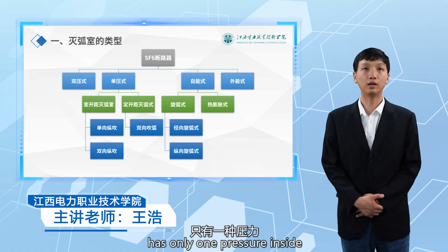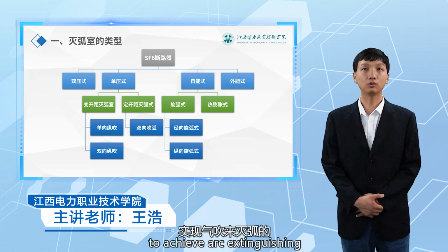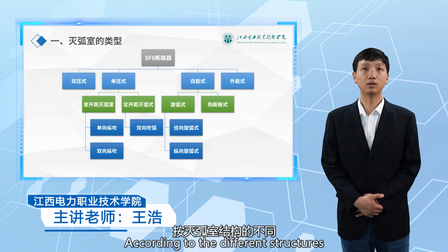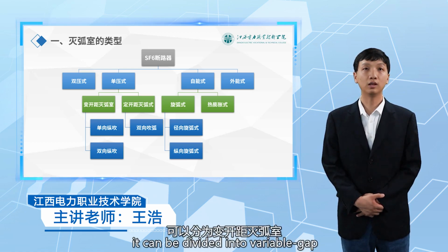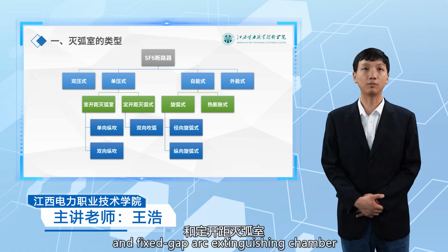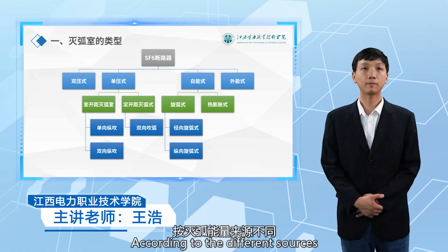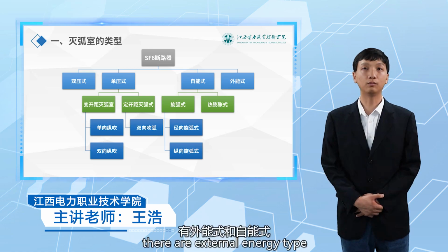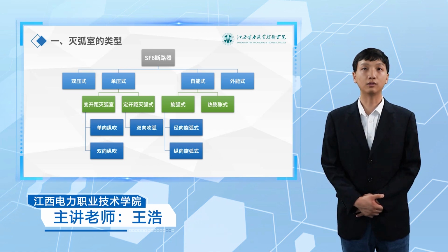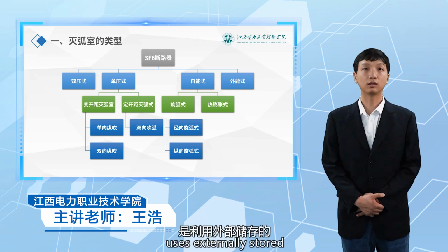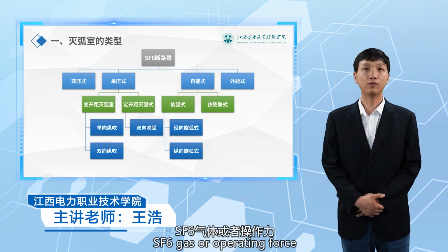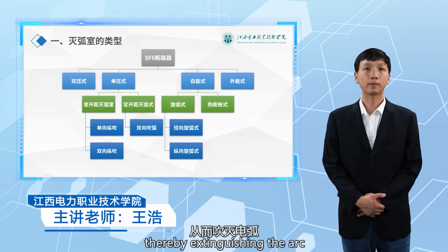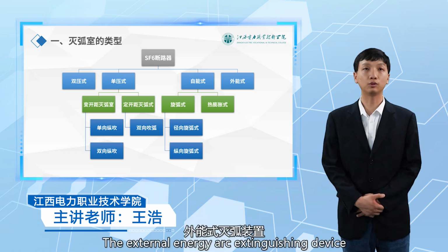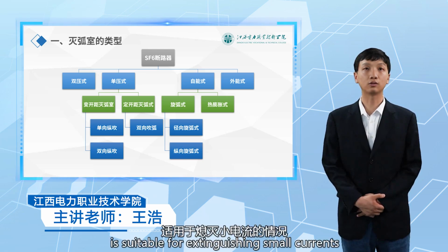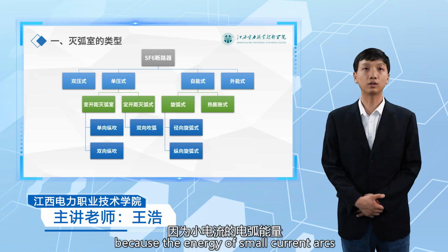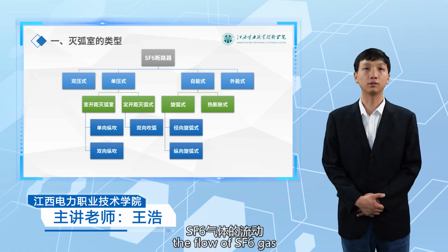The single pressure type has only one pressure inside. It relies on gas compression to achieve arc extinguishing. According to the different structures of the arc extinguishing chamber, it can be divided into variable gap arc extinguishing chamber and fixed gap arc extinguishing chamber. According to the different sources of arc extinguishing energy, there are external energy type and self-energy type. The external energy arc extinguishing device uses external stored sulfur hexafluoride gas or operating force to move the sulfur hexafluoride gas, thereby extinguishing the arc. The external energy arc extinguishing device is suitable for extinguishing small currents because the energy of small current arcs is not enough to drive the flow of sulfur hexafluoride gas.